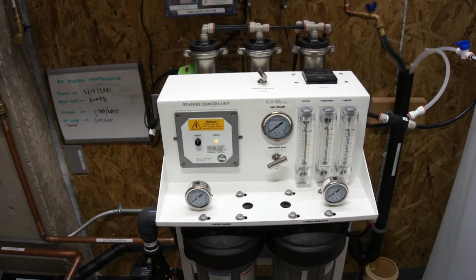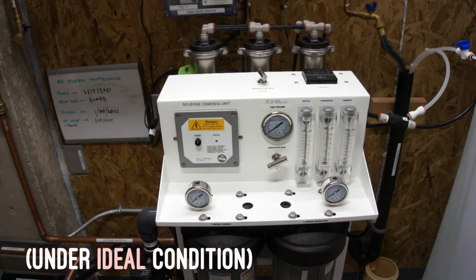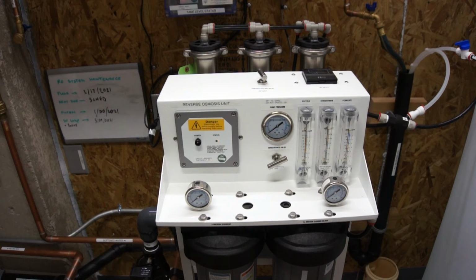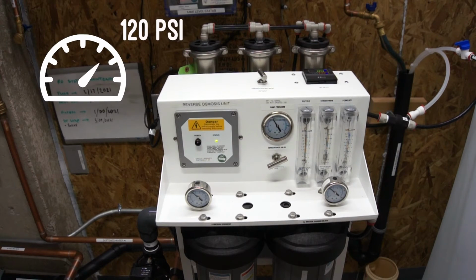This one is rated at 1,000 gallons per day. That is, under ideal conditions, it can produce 1,000 gallons of water per day. It has 3 RO membranes and uses a pump to push water through those membranes at 120 psi.